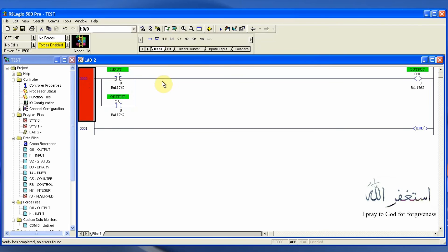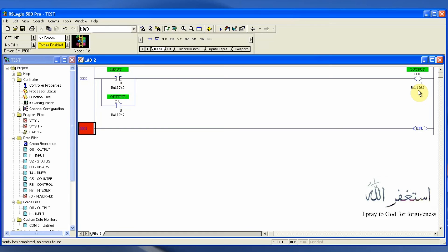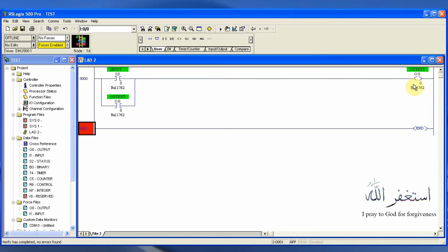When we press the I0/0 input, we will get our output O0/0 turned on. As soon as this output gets turned on, its auxiliary O0/0 normally open contact also turns on, completing the path and turning on our output O0/0 permanently — it gets latched.